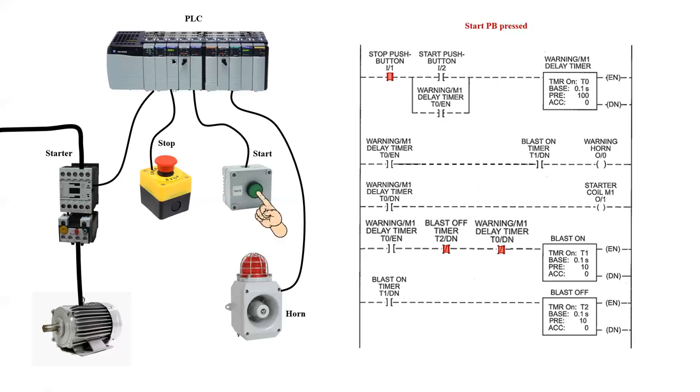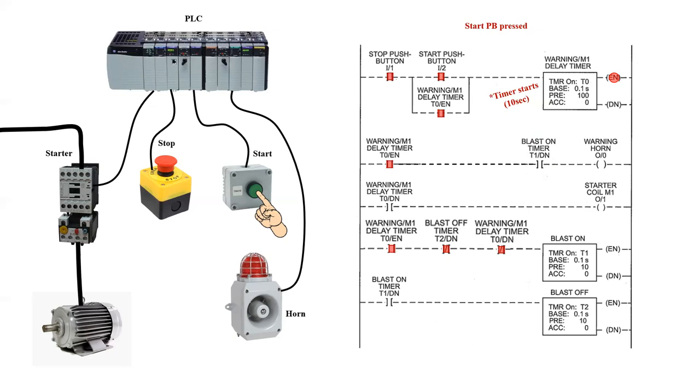Let's go ahead and press the start push button, and we're going to see a number of things take place. As soon as we do this, input two goes true, and my timer, M1 warning, will start to time. Now watch the enable coil on the right hand side will immediately go on, and it's going to start timing for 10 seconds.